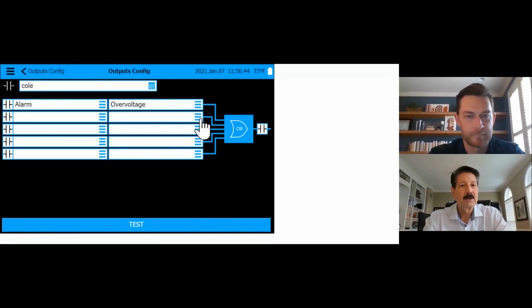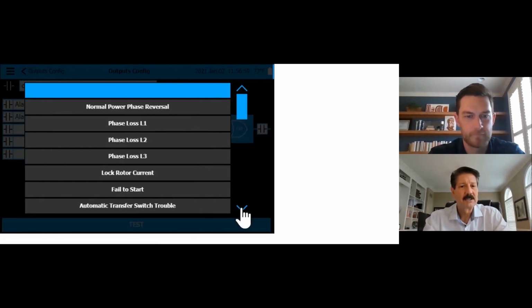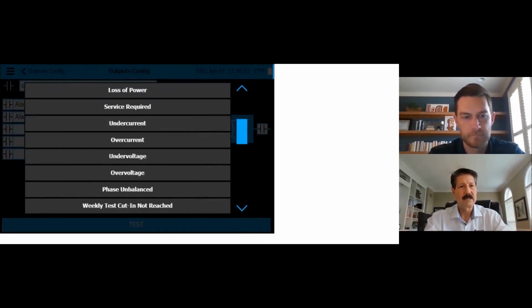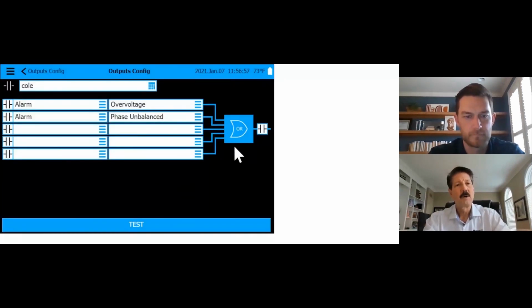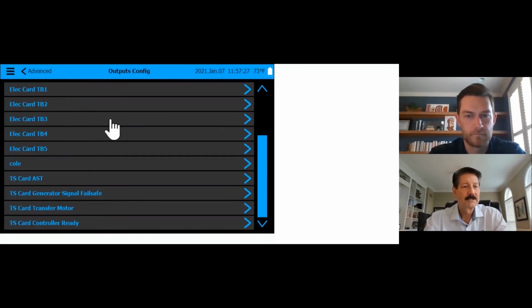So let's look at this. We could also add another one here. We can add an alarm here. And in addition to over voltage, I can go, well, let's take a look at phase unbalance. So if I have an over voltage or a phase unbalance, that contact will close. We can also change the status of this. Instead of or, one or the other, I can go and. So in order for the contact to close, I need both of them to be activated. So I need an over voltage condition and a phase unbalance to occur simultaneously for that contact to close. Makes sense. Just wanted to show that to you.